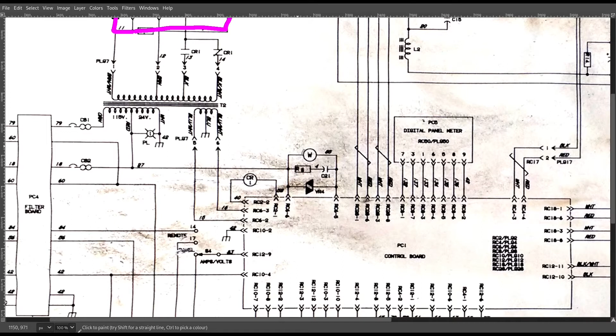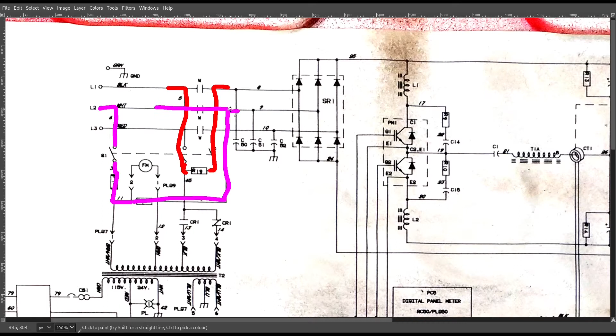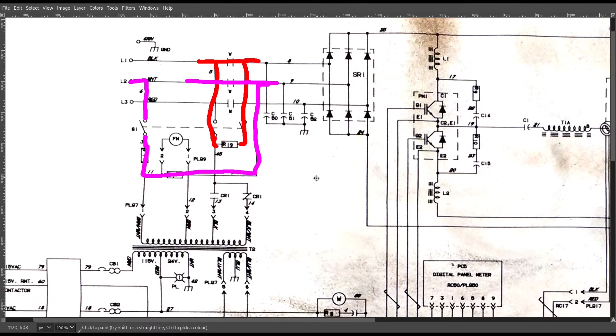And then this contactor here, W, is controlled from the main control board, and it's just a fixed delay. On mine it's about 6 or 7 seconds after power on, then it closes W, and then line 2 makes it directly, and same thing for L1. So these resistors don't matter anymore once the main contactor is energized.